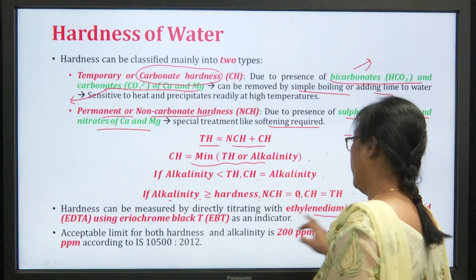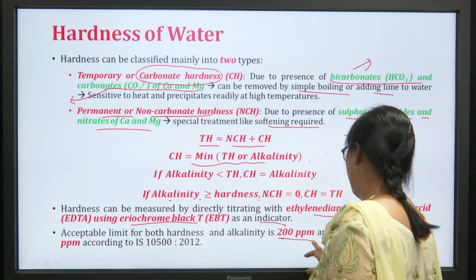Total hardness is equal to carbonate hardness plus non-carbonate hardness. Carbonate hardness is the minimum of total hardness or alkalinity. If alkalinity is less than total hardness, carbonate hardness is equal to alkalinity. If alkalinity is more than hardness, non-carbonate hardness is equal to 0 and carbonate hardness is equal to total hardness. Hardness can be measured by directly titrating with EDTA using Eriochrome Black T as indicator. The acceptable limit is 200 ppm and the permissible limit is 600 ppm for both hardness and alkalinity.